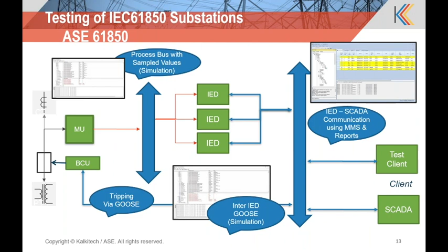And on the 61850 side, the detailed features include the discovery of IEDs. If you feed the IP address, it will discover the device configuration and provide everything for you. And the server functionality or server tool will be able to simulate the devices using their SCL files. Client tool can collect the data via poll, report, and Goose. And server simulator will be able to simulate the reports and Goose in the network.